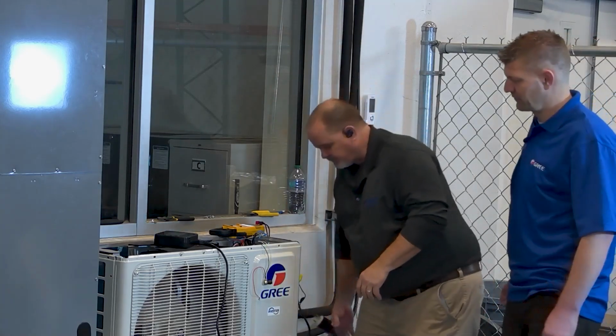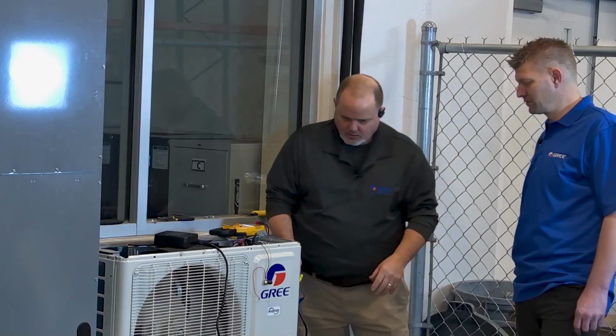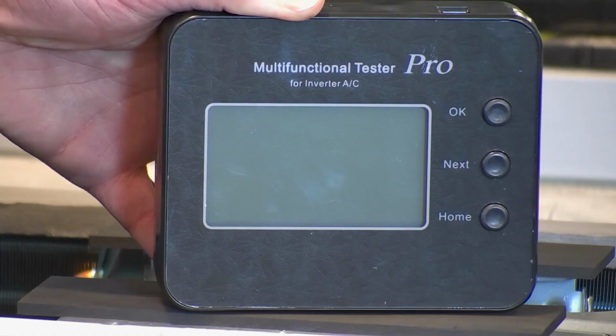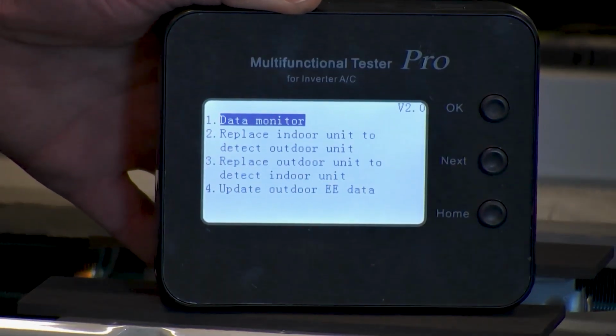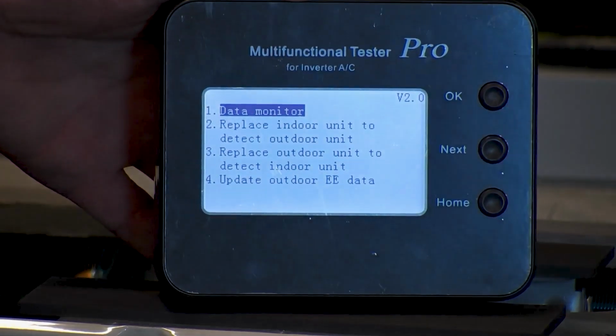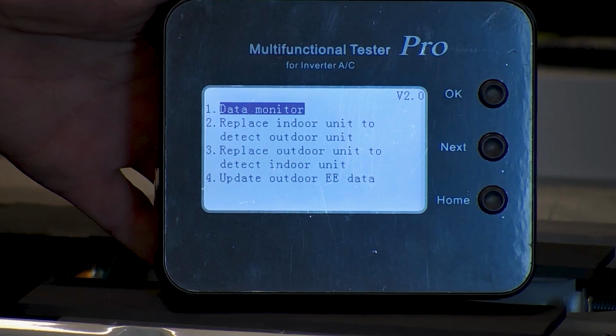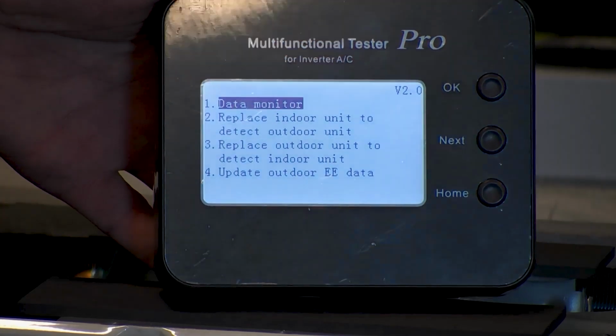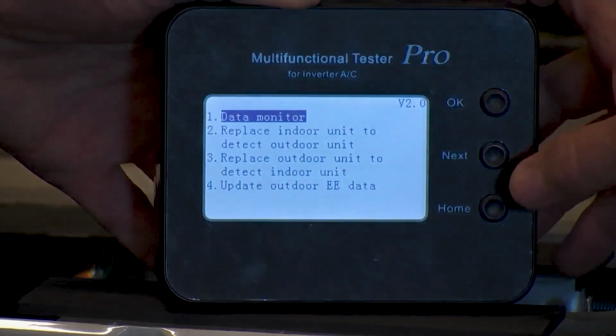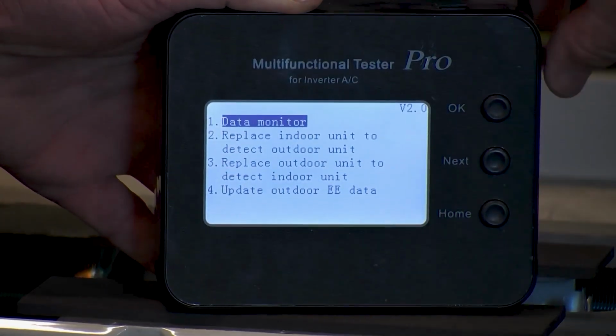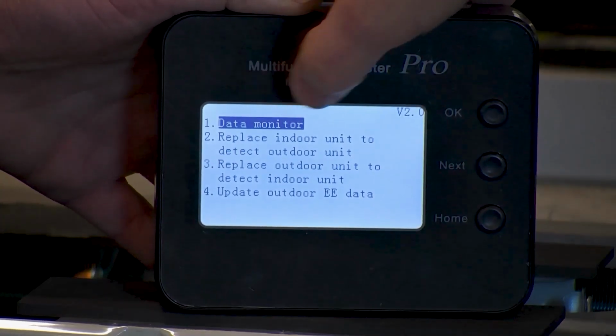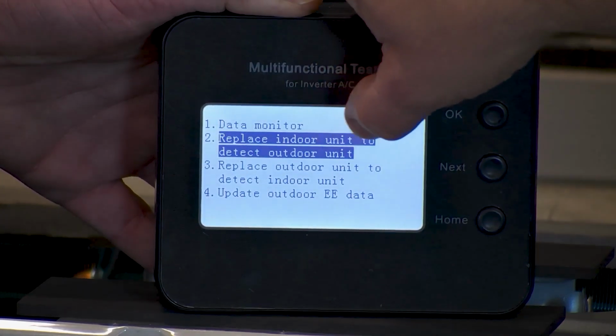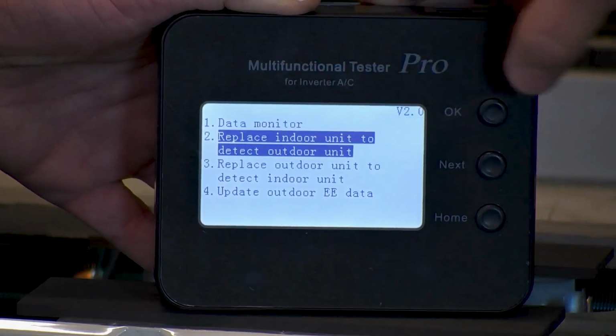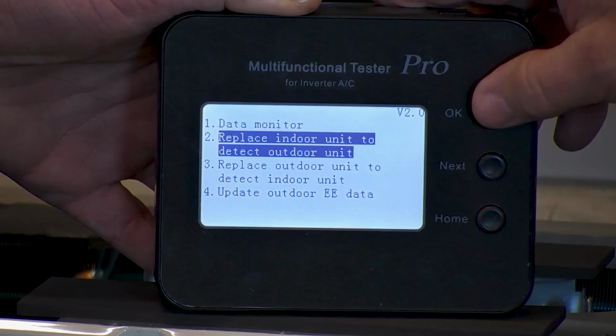We'll start with, let's simulate the indoor. All right, here we go, guys. We're going to get rolling here now. So we're going to simulate. I've disconnected the number 2 wire going to the indoor unit and only hooked up the service tool to the 2 wire to the outdoor unit. The tool comes up, and I want to make sure Nick's zeroed into it. It says data monitor, and then we can go to next. Now it says replace indoor unit to detect outdoor unit. That's what we want, so we're going to hit OK.